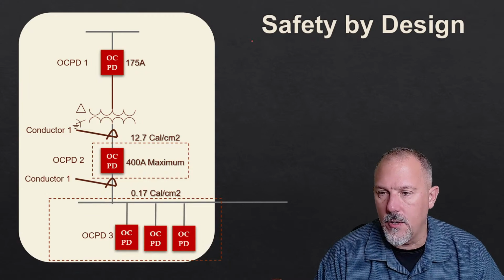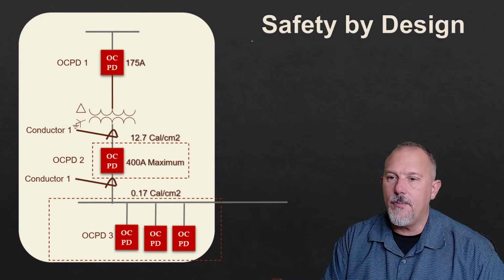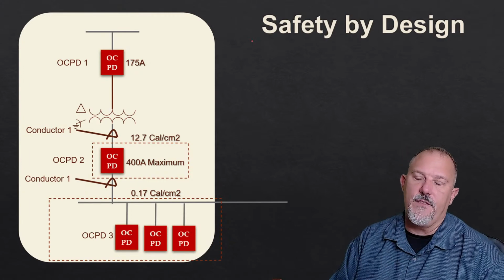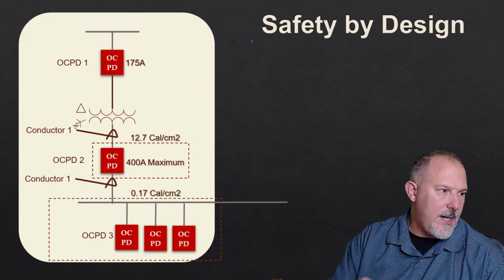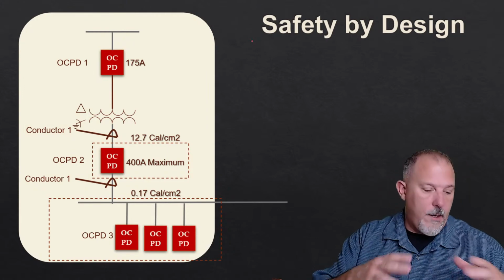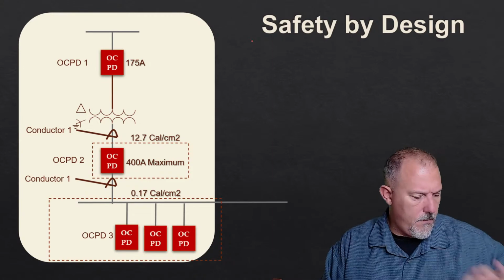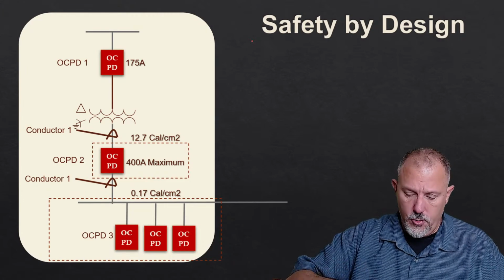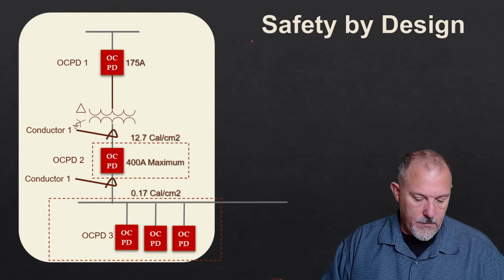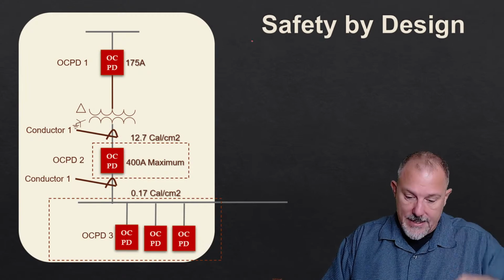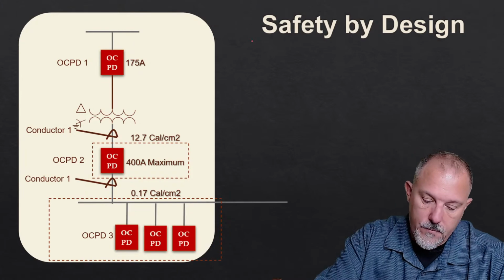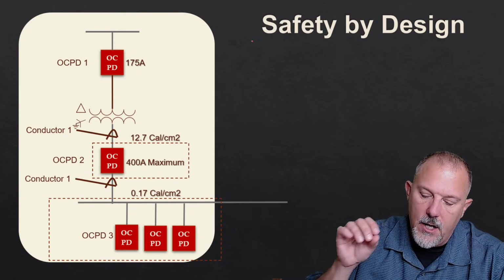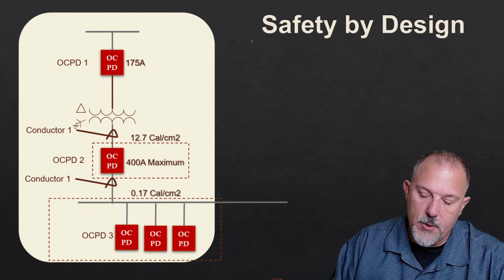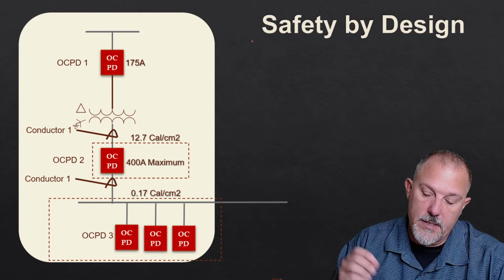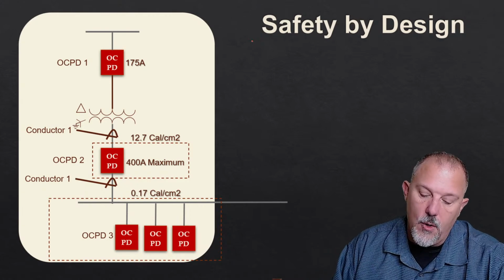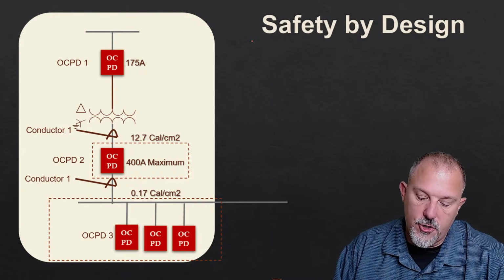Separated in the same panel board qualifies? No. So separated in the same panel board does not qualify, Felix. I would have to pull that out. It says separate enclosure. So, let's see, is enclosure a defined term? Yes. Enclosure is a defined term. The case or housing of apparatus, or the fence or walls surrounding an installation to prevent personnel from accidentally contacting energized parts or to protect the equipment from physical damage. See Table 110.28 for examples of enclosure types.